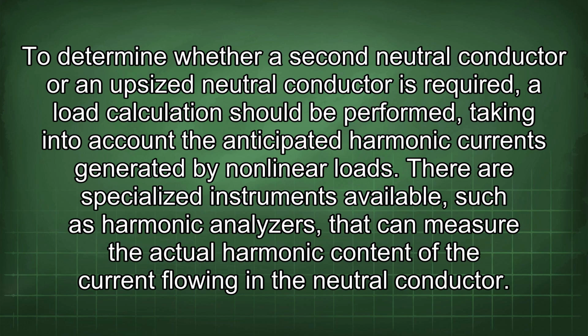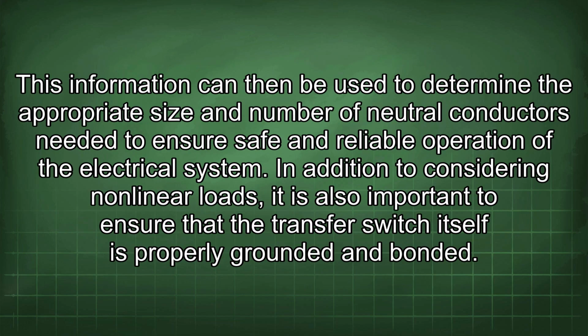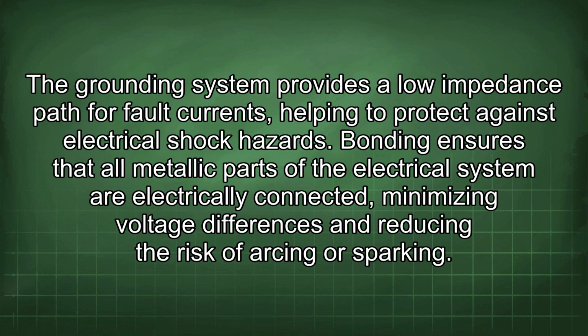To determine whether a second neutral conductor or an upsized neutral conductor is required, a load calculation should be performed taking into account the anticipated harmonic currents generated by nonlinear loads. There are specialized instruments available, such as harmonic analyzers, that can measure the actual harmonic content of the current flowing in the neutral conductor. This information can then be used to determine the appropriate size and number of neutral conductors needed to ensure safe and reliable operation of the electrical system. In addition to considering nonlinear loads, it is also important to ensure that the transfer switch itself is properly grounded and bonded. The grounding system provides a low impedance path for fault currents, helping to protect against electrical shock hazards.